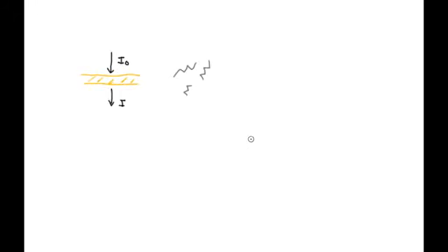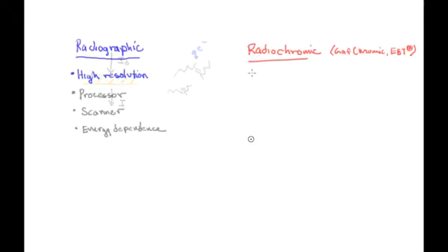Then you have a reaction that happens when radiation comes in. If you have a charge or an electron, there's a cross-linking of these monomers. The result of that cross-linking is that it becomes optically opaque. So the film darkens.